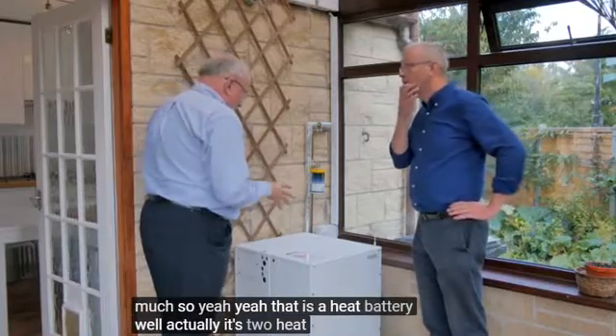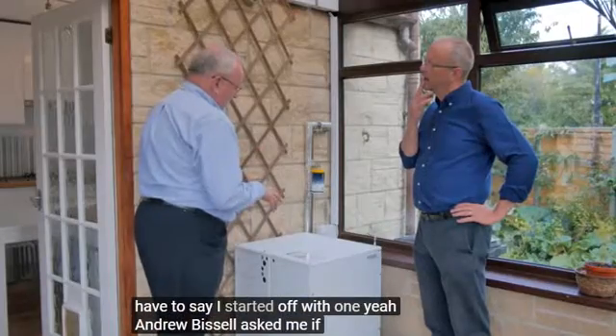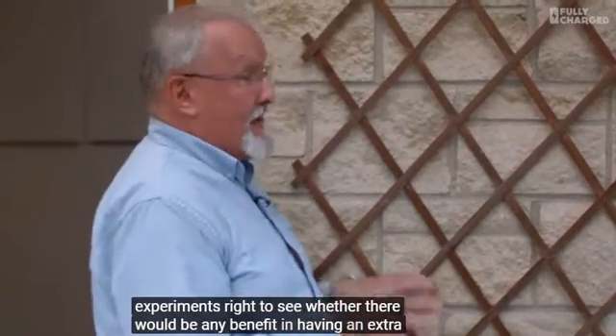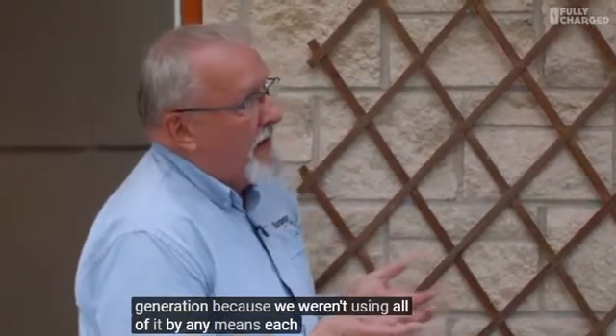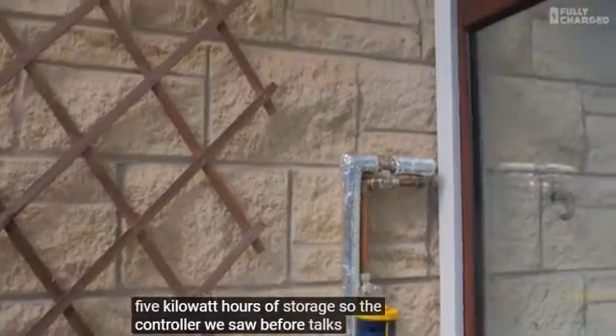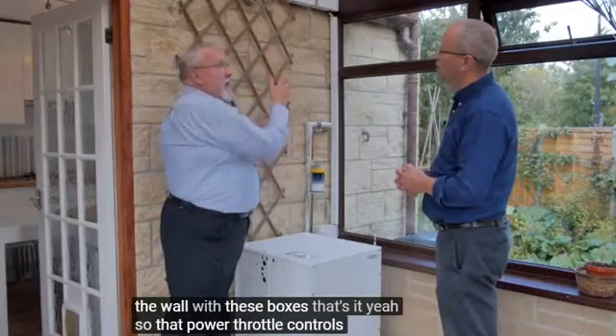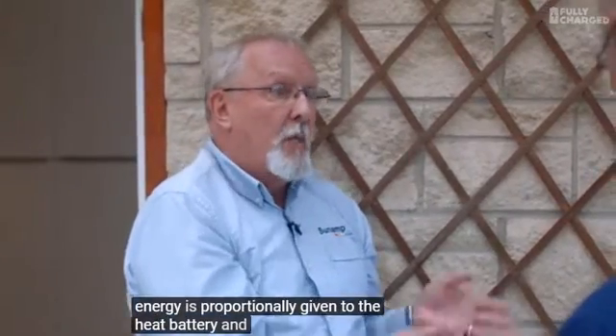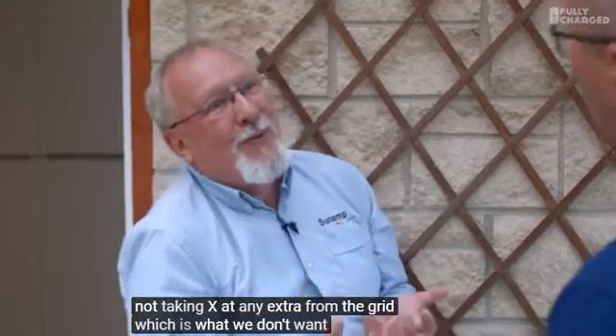That is a heat battery - well actually it's two heat batteries. I started off with one. Andrew Bissell asked me to do some experiments to see whether there'd be any benefit in having an extra one, to see if we could use more of my generation, because we weren't using all of it by any means. Each one of these is five kilowatt hours of storage. The controller we saw before talks wirelessly to the power throttle up on the wall here, and that power throttle controls how much energy is proportionally given to the heat battery.